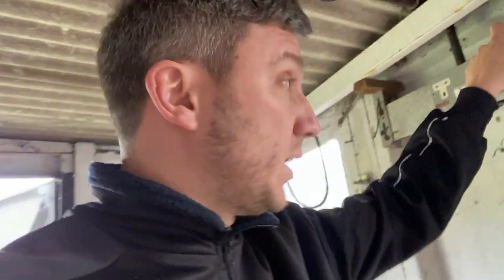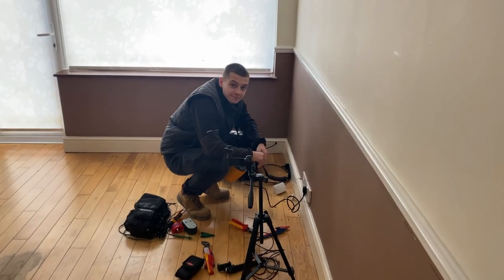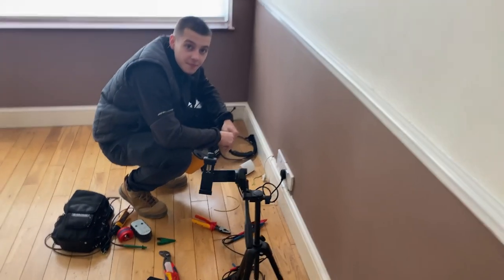It was probably tripping out at some point. Extension leads! You've got an extension lead here. Got my boy going around now getting some ZS readings of all the sockets.